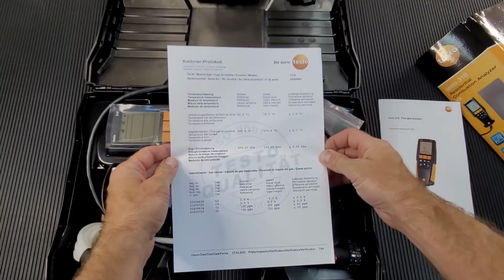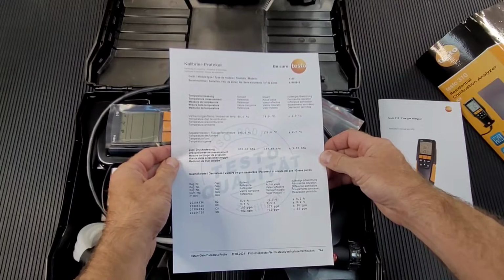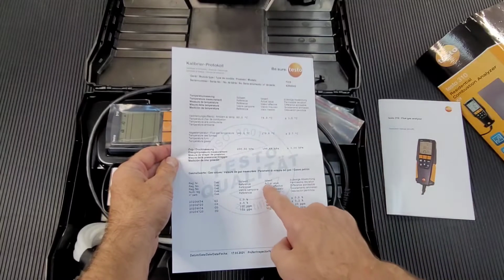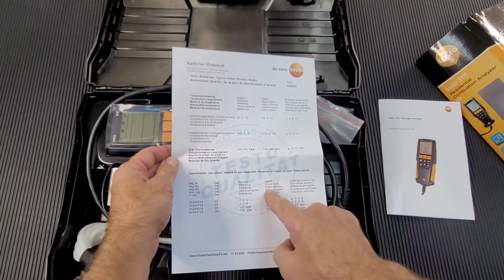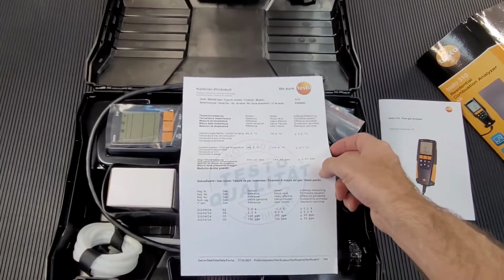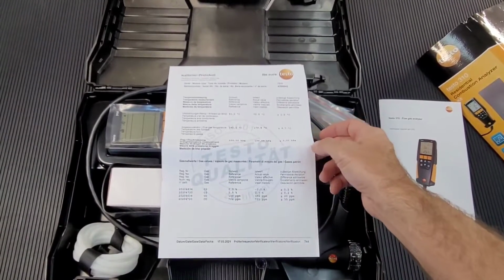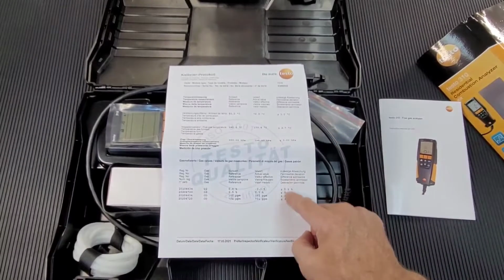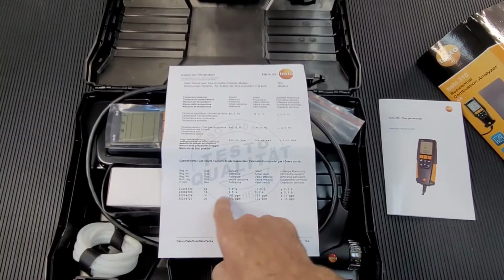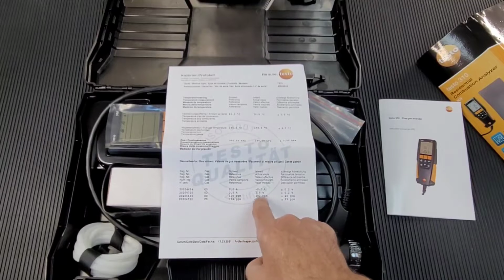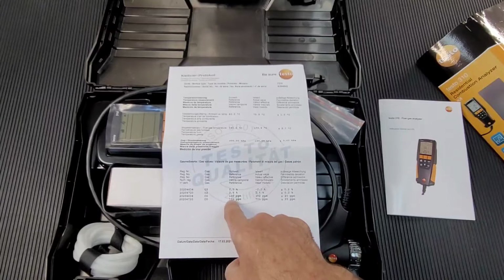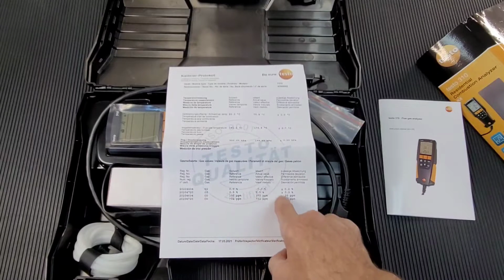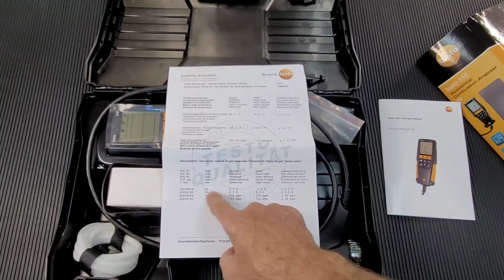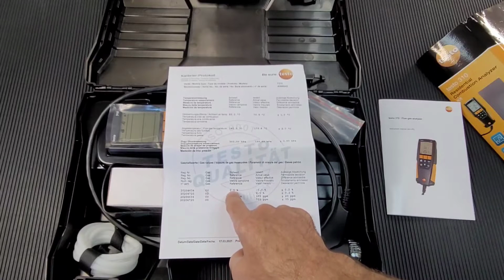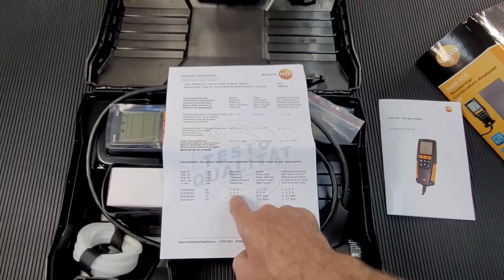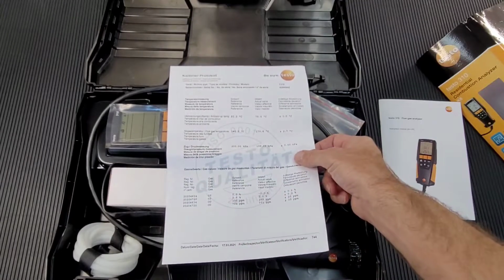Look, a very detailed calibration certificate with what actually happened, the reference, the actual value of calibration and their permissible deviation, what qualifies. In other words, they put 100 ppm, they get 102. They put CO at 702, they get 701. So they look also for the linearity, which is very nice. Likewise, for the O2, they do a 0.0, we get 0, and 2.5, 2.5, very elegant.